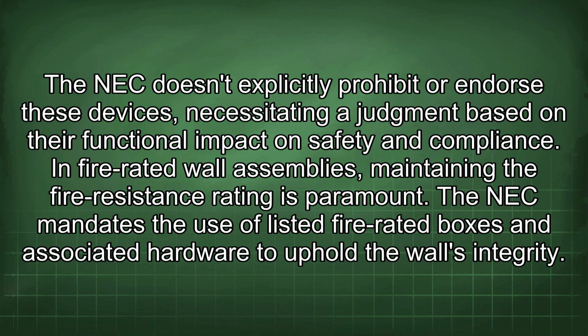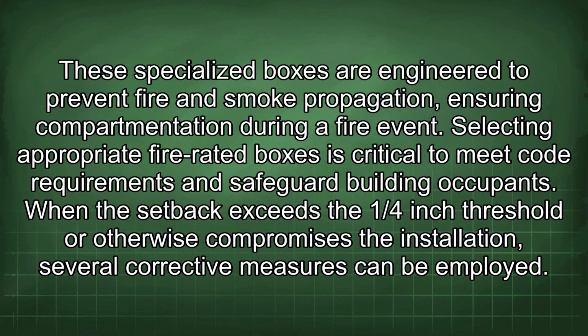The NEC mandates the use of listed fire-rated boxes and associated hardware to uphold the wall's integrity. These specialized boxes are engineered to prevent fire and smoke propagation, ensuring compartmentation during a fire event. Selecting appropriate fire-rated boxes is critical to meet code requirements and safeguard building occupants.